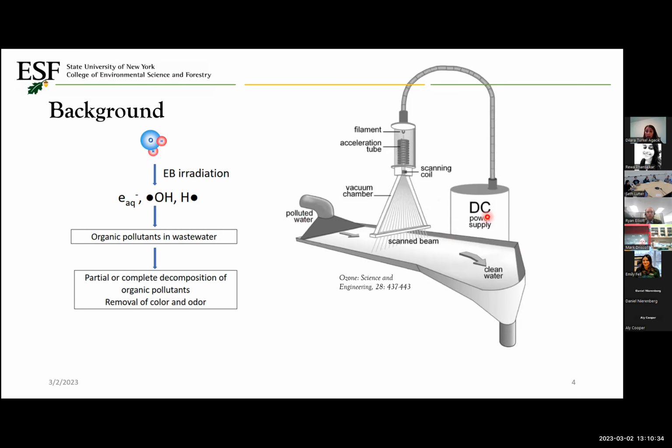In the image shown on the right, there is a schematic view of an electron beam accelerator in the wastewater treatment plants. The E-beam originates from a heated filament, which is under high voltage from the power supply. It is focused and accelerated within an evacuated acceleration tube, reaching an energy corresponding to the output voltage of the power supply. In the accelerator, the electron beam passes the anode through a hole, and it enters a vacuum chamber where it is scanned by a varying magnetic field. Then the scanned beam passes through a thin window to meet the water being processed.